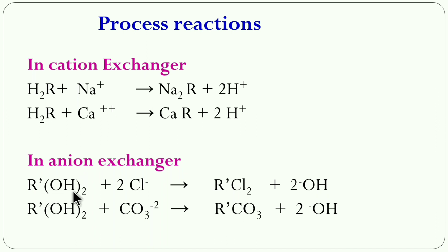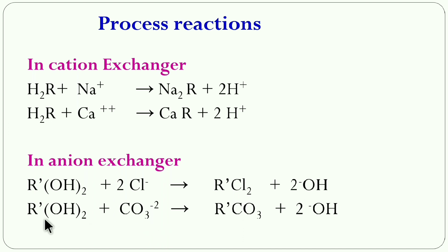For the anion exchanger resin, represented as R'(OH)₂: when Cl⁻ ions are present, they react with R'(OH)₂ to form R'Cl₂ and release OH⁻ ions. Similarly, when CO₃²⁻ (carbonate) ions are present, R'(OH)₂ reacts with CO₃²⁻ to form R'CO₃ and release 2 OH⁻ ions. In this way, OH⁻ ions are released into the water while all anions are captured by the anion exchanger resin.